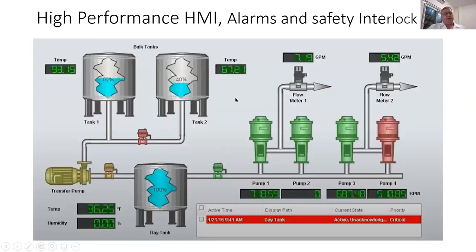The change happened some years later, when people saw that this kind of graphics is not really efficient, because they are overloaded and people don't get the right information at the right time. So for example, this pump has a color and another color when it runs or not, or the valve here, this is red, this is orange, this is green. So nobody knows really what the meaning of that is.